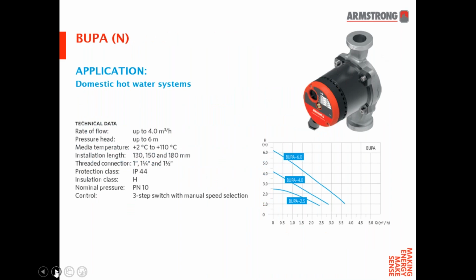So moving on to the next product, which is the BUPA-N. Here, the application is purely just domestic hot water systems. Rate of flow up to 4 cubic meters an hour. Pressure head up to 6 meters. Media temperature 2 degrees centigrade up to 110 degrees centigrade. And installation lengths 130 millimeter, 150 millimeter, and 180 millimeter. So that's the face-to-face dimension of the body. And again, it being for hot water, it's a stainless steel body that we're using here rather than cast iron.